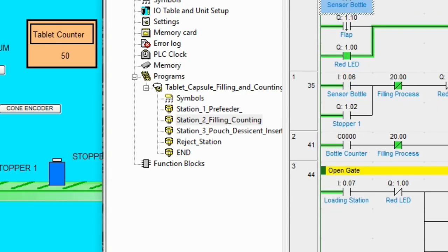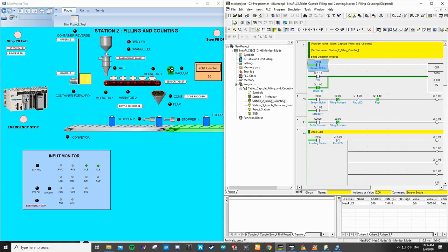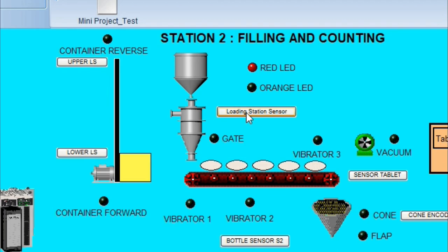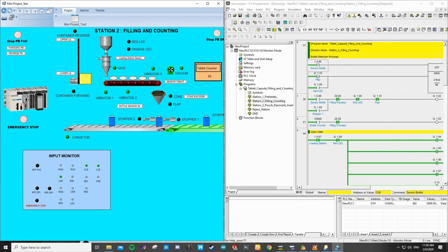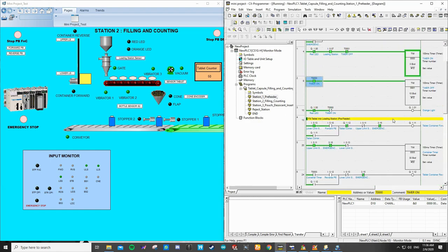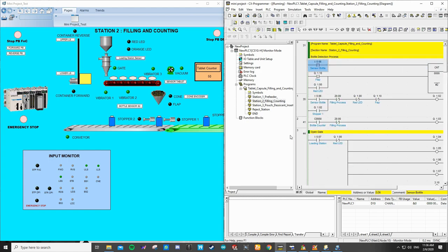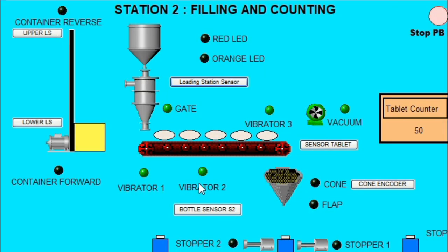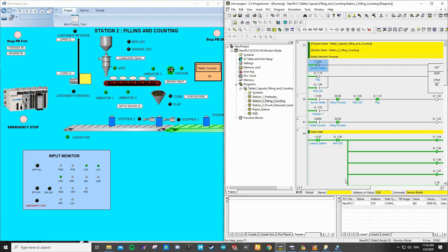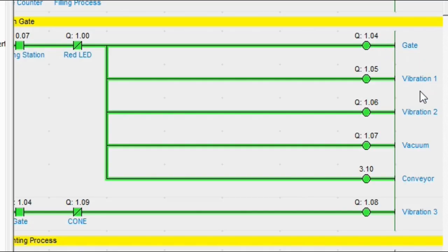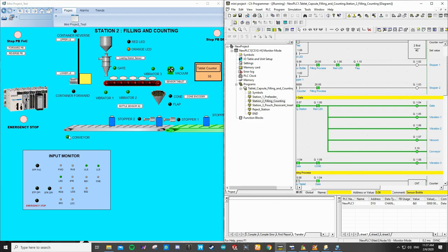After the Pre-Feeder process is finished, we go into the filling and counting process. For the loading station sensor, it will be detected after the tablet and capsule fill into the silo. From the Pre-Feeder, the orange LED will be blinking for one second, then proceed into filling and counting. After the loading station sensor detects the tablet and capsule, the gate, all vibrators 1, 2, and 3, and the vacuum inside the silo will be turned on. As you can see on the CS Programmer, all the gate, vibration, vacuum, and conveyor are also turning on.